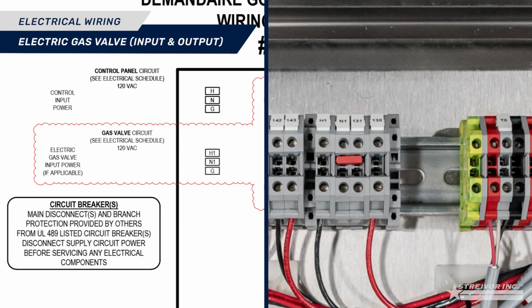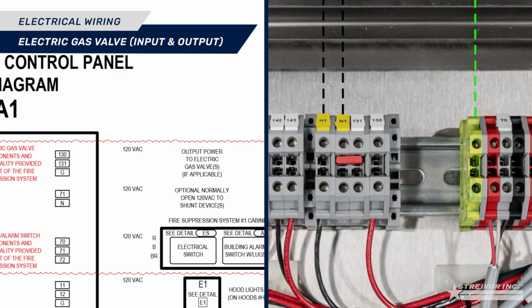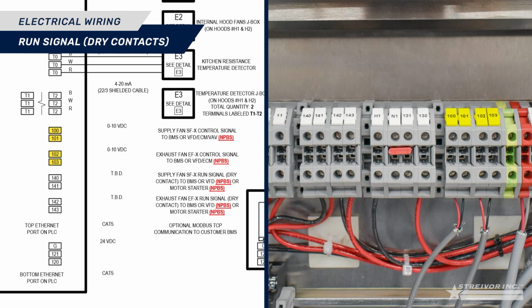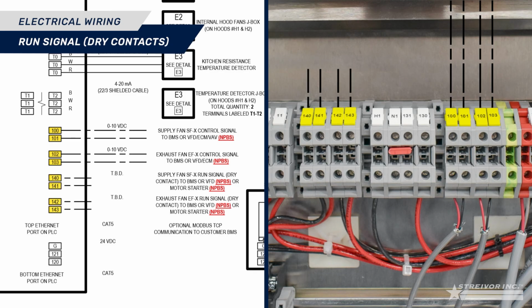To supply input power to the gas valve if applicable, connect the 120 VAC single-phase power to the designated terminal blocks in the control panel labeled H1, N1, and ground. To supply output power to the electric gas valve, connect the designated terminal blocks in the control panel labeled 130, 131, and ground to the electric gas valve. Repeat this process for additional electric gas shutoff valve circuits if applicable. Connect the terminal blocks in the control panel designated for fan control signals, and run signal dry contacts to the appropriate external destination.